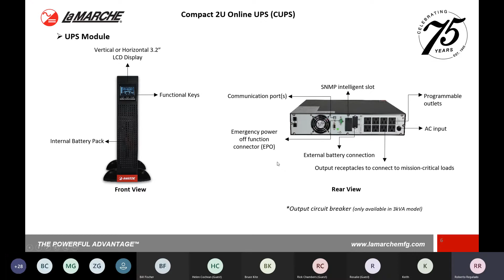Moving on to the battery pack for the compact UPS. You have the preference of using just the internal battery pack, which gives you a much smaller runtime, or you can use an external battery connection to multiply your backup time depending on your load capacity. We tried to make it modular and scalable so you can play with those times. Typical backup time for this type of application is anywhere from 5 to 30 minutes, usually. Anything above that, you're probably better off using an external battery pack or battery rack, since that's going to be a much larger battery compared to the smaller battery packs currently available for the compact UPS.